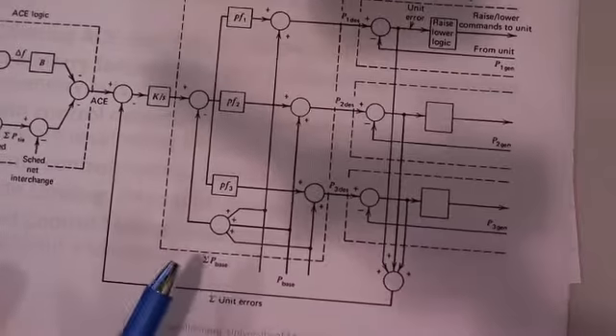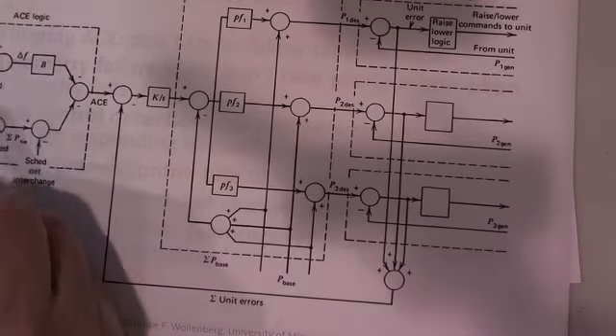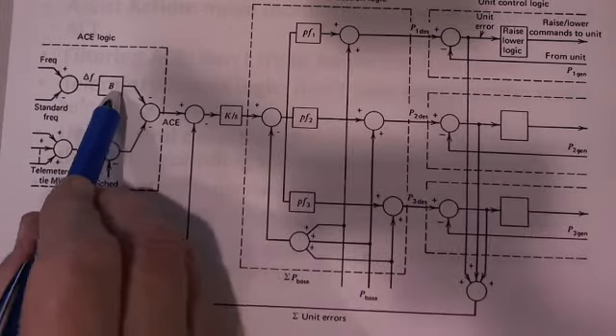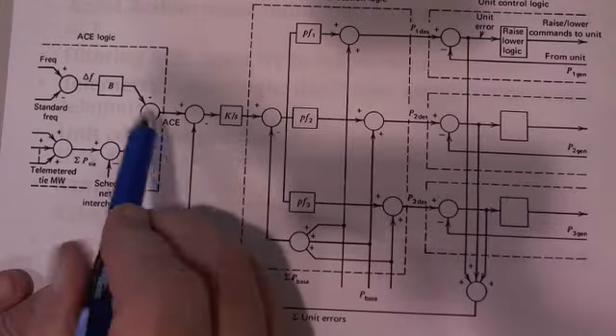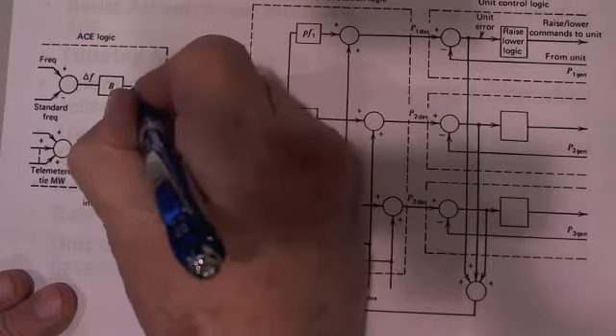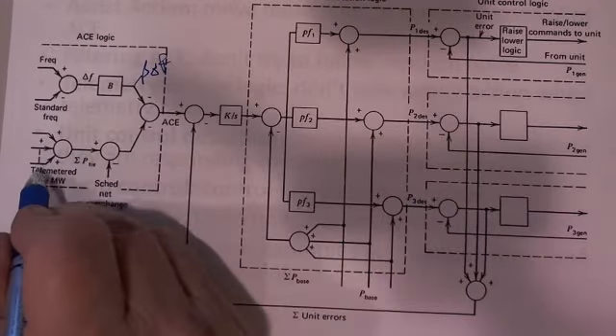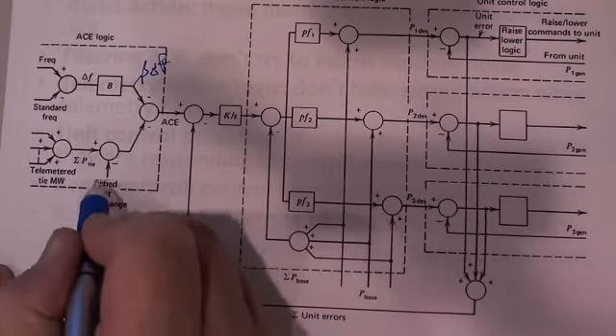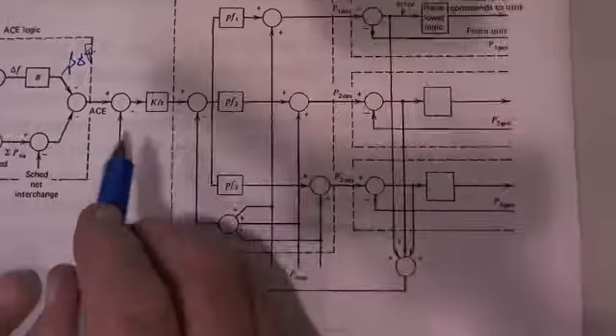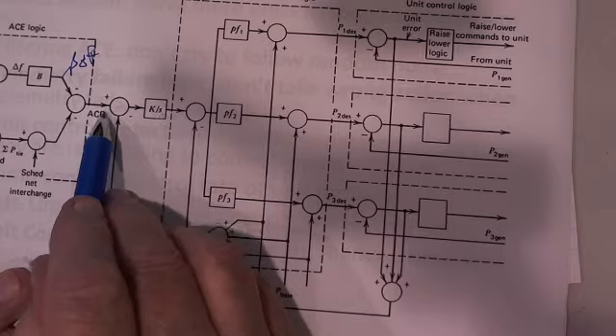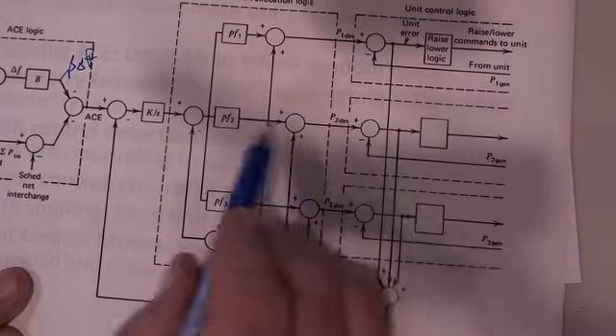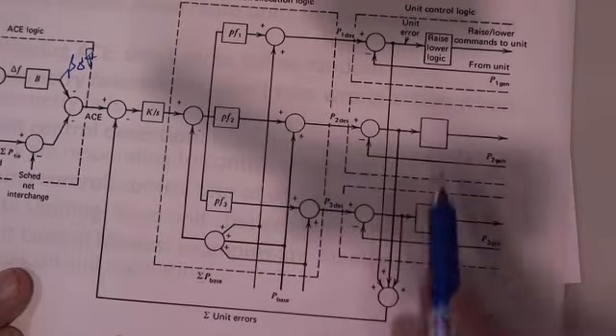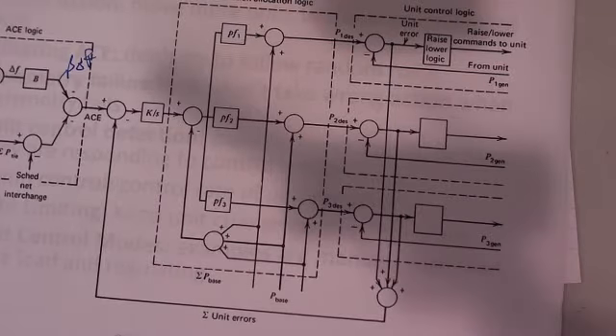This is a very crude diagram. Here's frequency, standard frequencies. We get delta frequency times bias. So this thing here is bias times delta F. Here's all the tie flows measured, and then there's a scheduled net interchange, and that gives me an ACE signal. And then this is the AGC that allocates right down to the generators themselves.